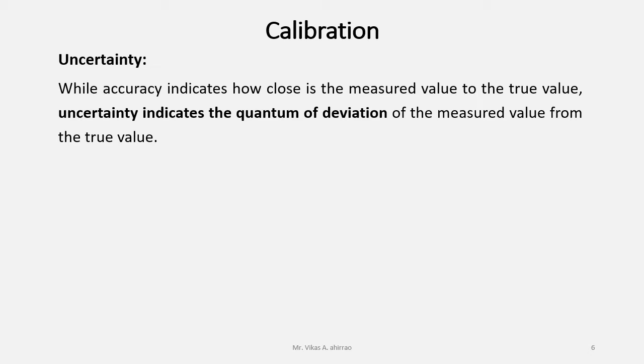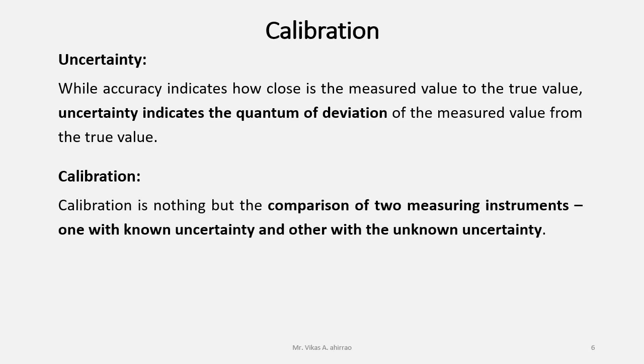Before going to the definitions of calibration, we will go for a very short term, that is uncertainty. While accuracy indicates how close the measured value is to the true value, uncertainty indicates the quantum of deviation of the measured value from the true value. Now, calibration is nothing but the comparison of two measuring instruments, one with known uncertainty and the other with unknown uncertainty.